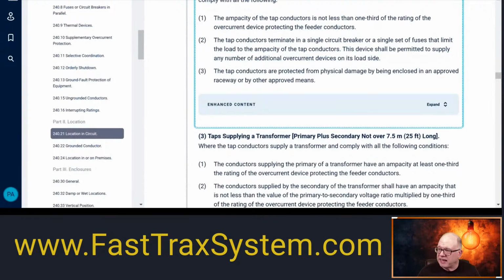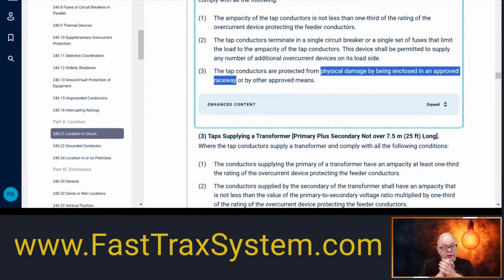All right, last caveat right here. The tap conductors are protected from physical damage by being enclosed in an approved raceway. Here's where the inspector gets involved. An approved raceway, well, I'd like to say listed raceway because most raceways are listed. However, there are some that are not required to have a listing. Certain wireways, for example, are not required to have a listing. So approved raceway means your inspector gets to look at it and make the decision, assuming it is a raceway or qualifies as a raceway, and they'll say, I'm okay with this.